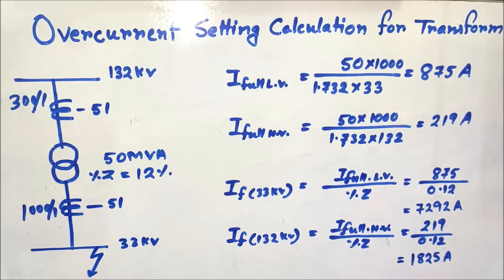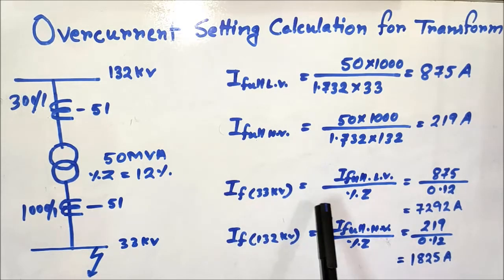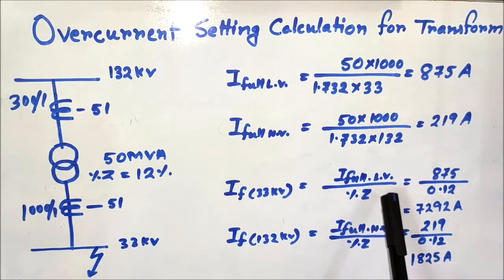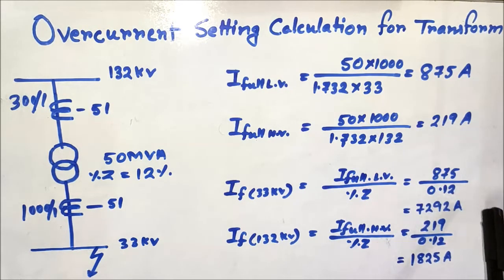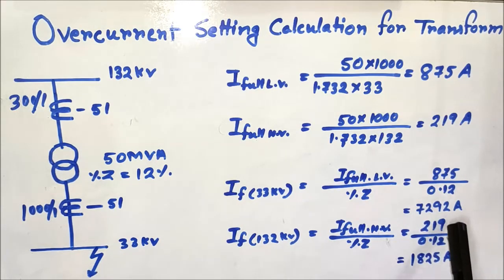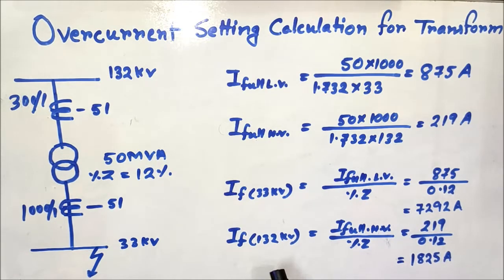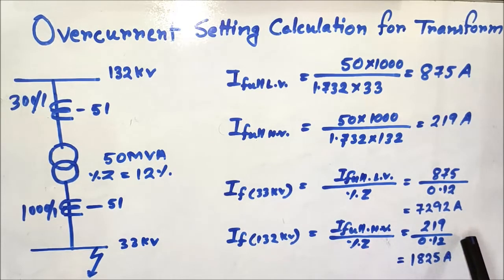Now, for a three-phase fault occurring exactly on the 33kV bus, the fault current on the LV side is equal to the full load current divided by percentage impedance: 875 divided by 0.12, which gives 7292 amperes, or 7.292 kilo-amperes. On the HV side, the reflected fault current is 219 divided by 0.12, which comes to 1825 amperes, or 1.825 kilo-amperes.